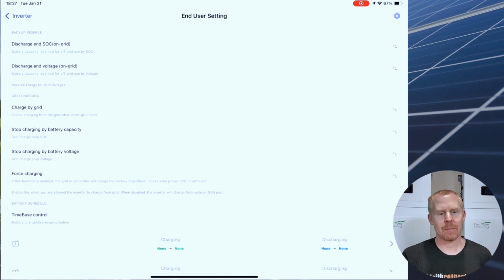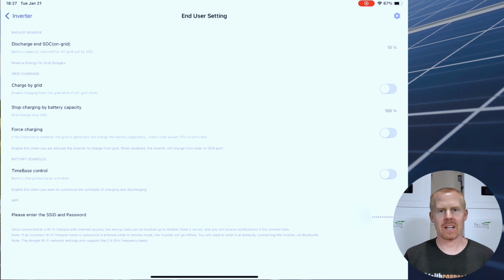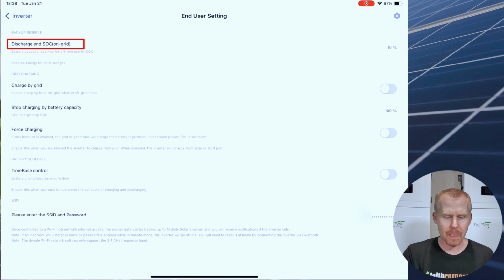They have this concept of end user settings versus installer settings. Some systems have this, some systems don't. It's more designed for installers and giving the actual homeowner some measure of control without being able to really mess the system up. Looking at this very first one, discharge end SOC on grid. This is going to be kind of like the floor that you want to use of your battery before it switches over to grid.